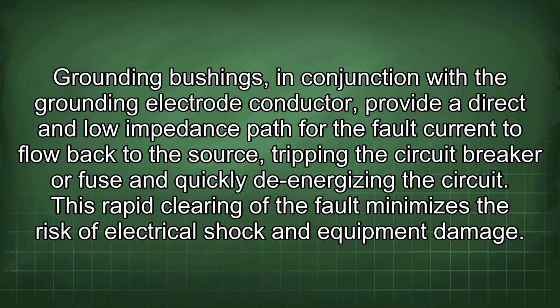Grounding bushings, in conjunction with the grounding electrode conductor, provide a direct and low impedance path for the fault current to flow back to the source, tripping the circuit breaker or fuse and quickly de-energizing the circuit. This rapid clearing of the fault minimizes the risk of electrical shock and equipment damage.